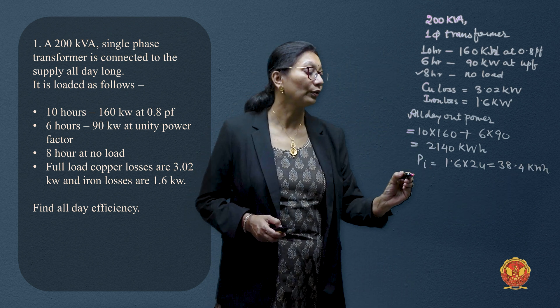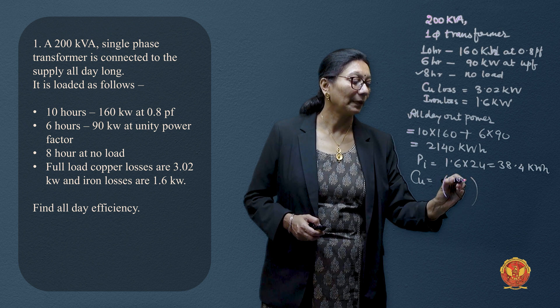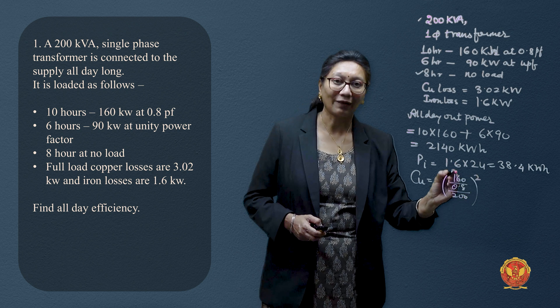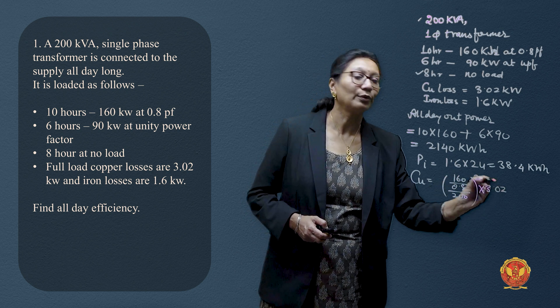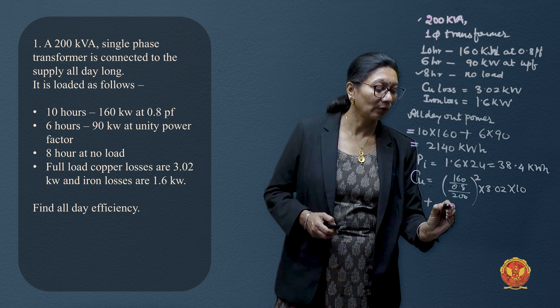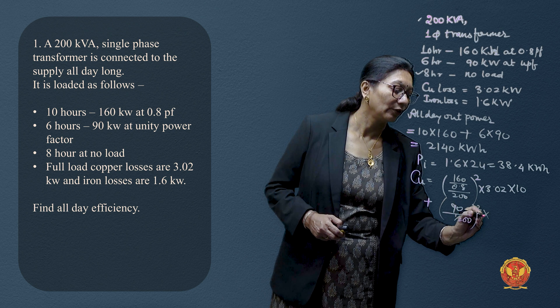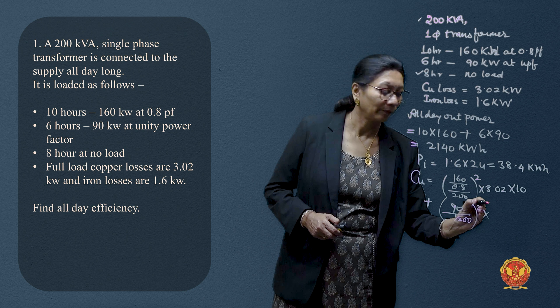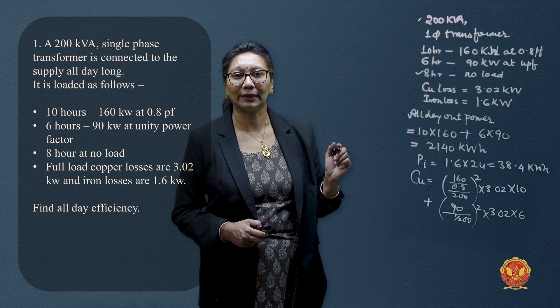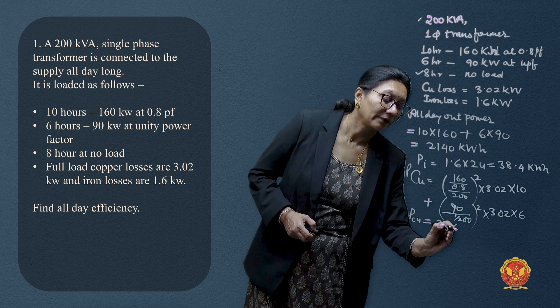Copper losses for 24 hours vary with load. For the first period: (160 / 0.8 / 200)² × 3.02 × 10 hours. For the second period: (90 / 1 / 200)² × 3.02 × 6 hours. For the third period (no load), copper losses are zero since there is no load on the secondary. This gives total copper losses of 33.87 kWh.